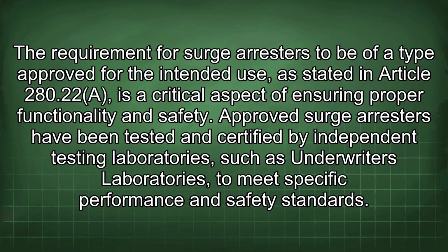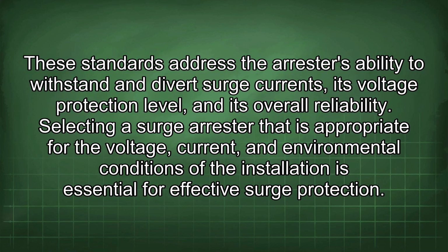The requirement for surge arresters to be of a type approved for the intended use, as stated in Article 280.22a, is a critical aspect of ensuring proper functionality and safety. Approved surge arresters have been tested and certified by independent testing laboratories, such as Underwriters Laboratories, to meet specific performance and safety standards. These standards address the arrestor's ability to withstand and divert surge currents, its voltage protection level, and its overall reliability. Selecting a surge arrestor that is appropriate for the voltage, current, and environmental conditions of the installation is essential for effective surge protection.